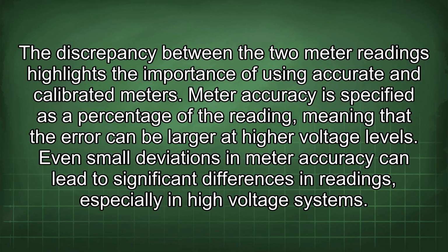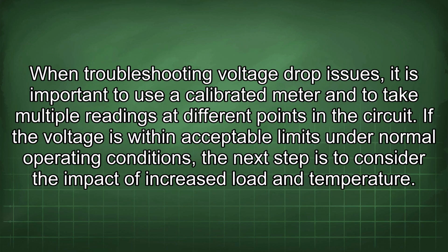Meter accuracy is specified as a percentage of the reading, meaning that the error can be larger at higher voltage levels. Even small deviations in meter accuracy can lead to significant differences in readings, especially in high voltage systems. When troubleshooting voltage drop issues, it is important to use a calibrated meter and to take multiple readings at different points in the circuit. If the voltage is within acceptable limits under normal operating conditions, the next step is to consider the impact of increased load and temperature.